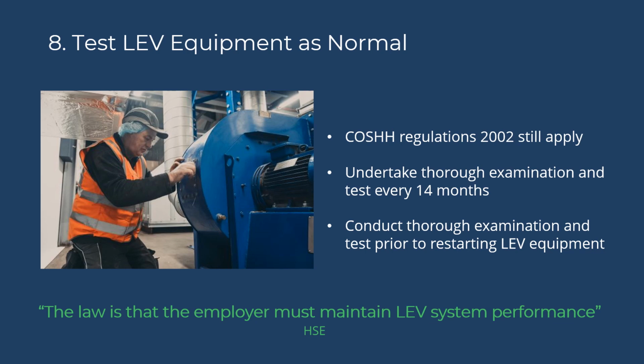The British Occupational Hygiene Society states that a thorough examination and test of each LEV system is required at a minimum frequency of every 14 months in order to comply with the law. If your process and machinery are not currently operating, according to HSE guidelines, an LEV system should be subject to a thorough examination and test prior to restarting. The position with regard to LEV at this time is constantly under review.